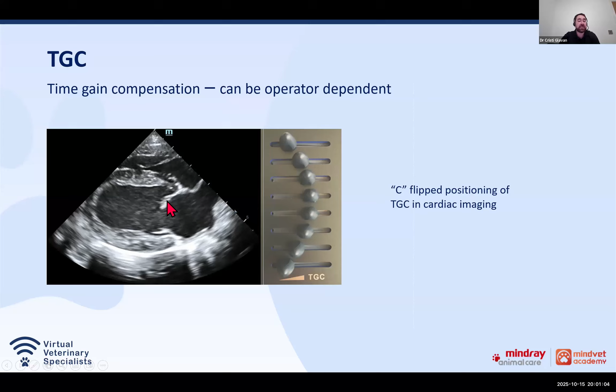Another setting, similar to the time gain compensation, is called lateral gain compensation. You will not find this on all machines, but I always emphasize it because it can give us really good image quality. Compared with the time gain compensation, it acts at a different level, in a different type of line, if that makes sense. Instead of going like that, as with the time gain compensation, this one will increase the gain vertically. So from the lateral part of the area that we are scanning, we can increase and decrease the resolution at different levels. It's really good if we want to see more structural changes.